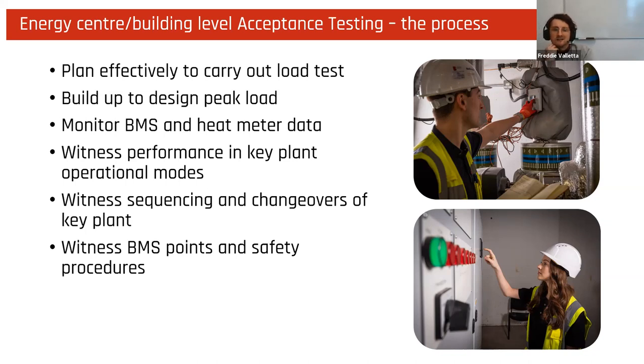Once all the plant room equipment is commissioned separately and a sufficient number of endpoints are connected to the network and commissioned correctly as well, the load test can be undertaken. We'd recommend that this is carried out with the BMS engineers and also boiler or heat pump manufacturers on site to ensure that any adjustments can be made there and then based on the performance observed. Load is introduced gradually onto the system, building up to that design peak load.